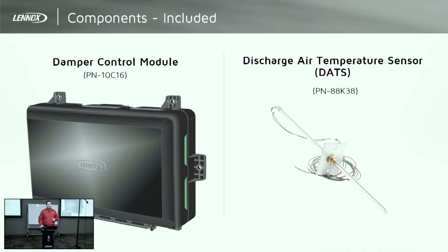In the box, we're going to get the damper control module and the discharge air sensor. That comes in every one. The discharge air sensor, I always like to tell guys, it really runs the show. Everything that this guy does, as far as sequence of operations, it's going to look at that discharge air temperature. That's the most critical component here.